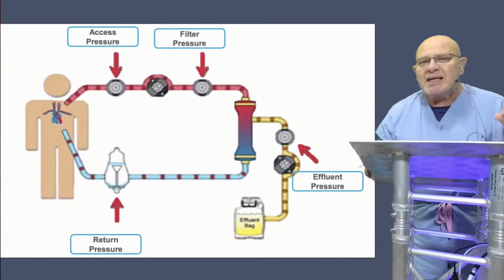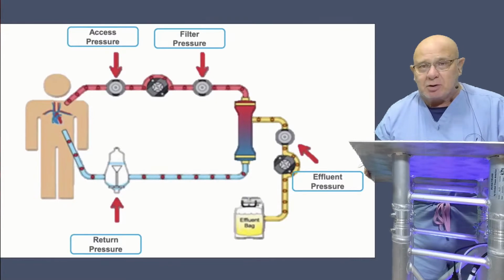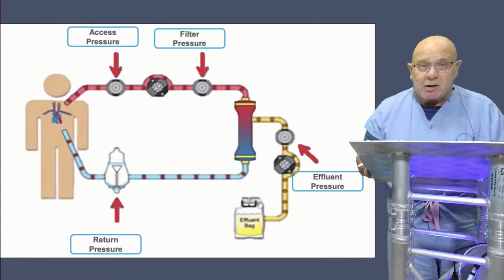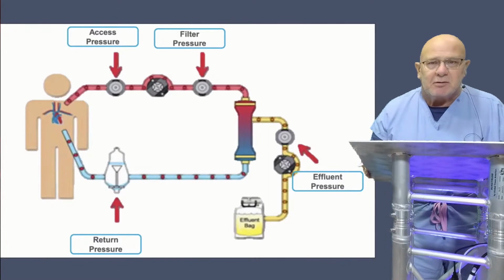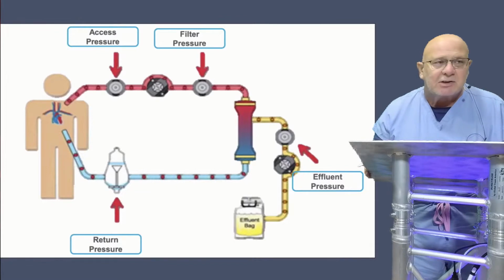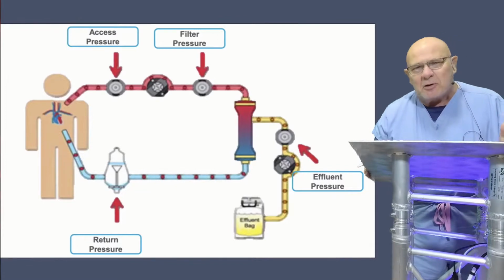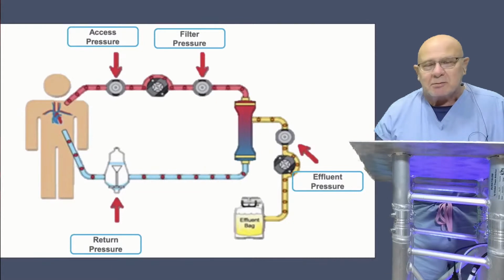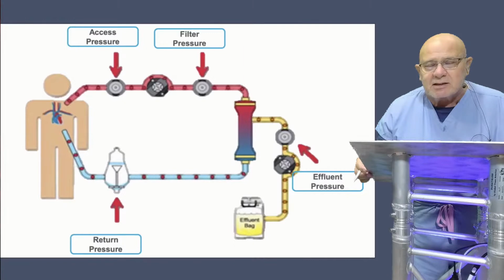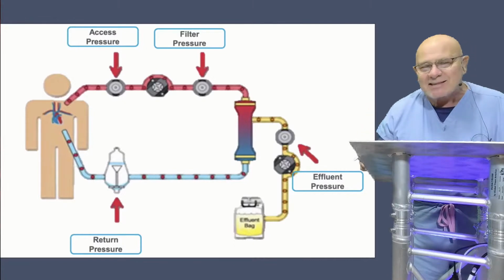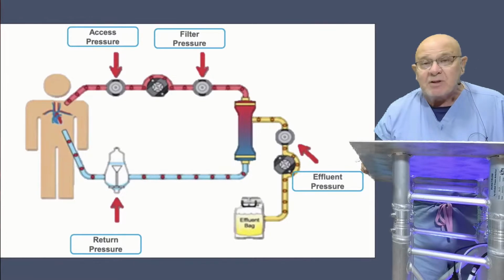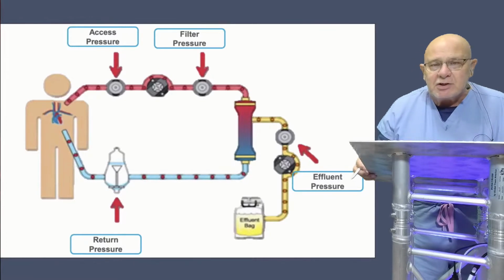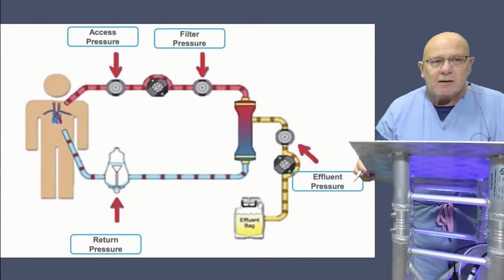So taking all of those things into consideration, the final thing I would like to say is that integrating a CRRT machine into your ECMO circuit is off-label for the CRRT machine, or the manufacturers. It's off-label for their intended purpose of their technology. It's also off-label for ECMO. So it's a double off-label conundrum, but it is certainly clinically and in terms of managing patients a much better alternative than the risk of sticking that patient and having an access catheter that doesn't work very well, because that is the number one cause of failure in the use of CRRT is, in fact, access problems. So keep that in mind.